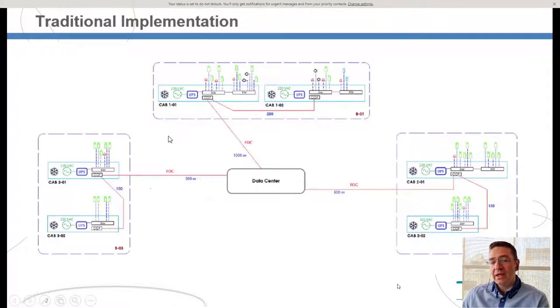So what we actually saved for the customer is all the connections, the power network that should have been built to provide all these cabinets with AC power. That's a lot of saving, a lot of power cable eliminated. We cut the need for AC cooling and UPS. So along with the saving on the AC power network, we also reduced the number of elements needed within each cabinet.